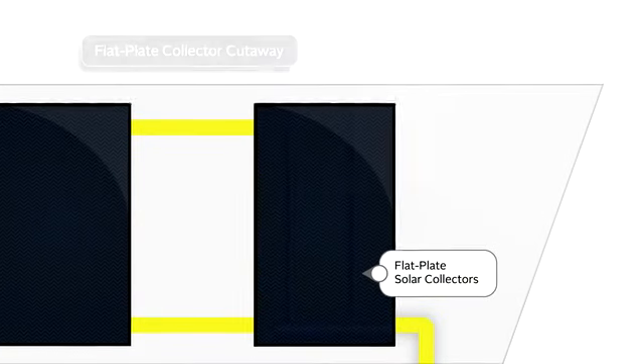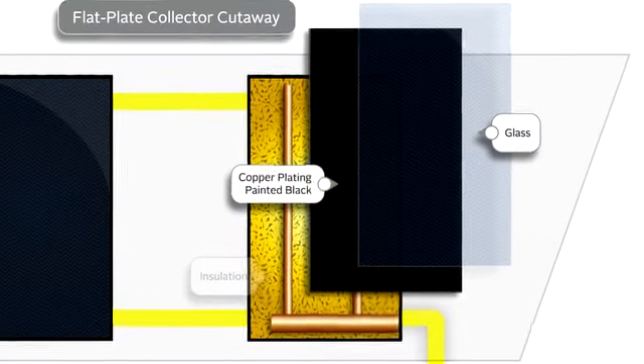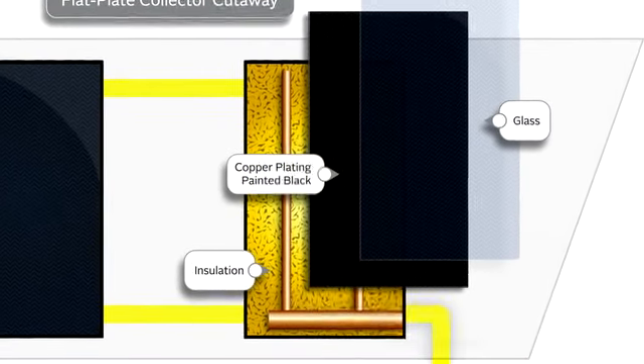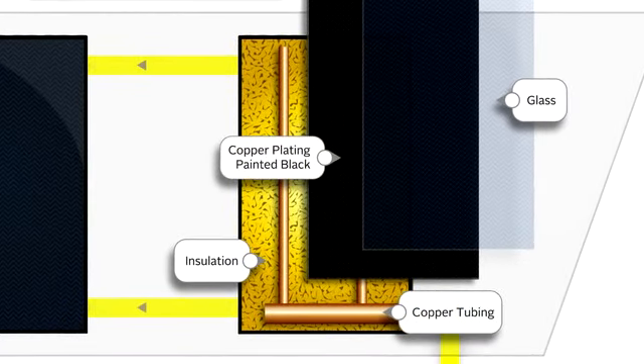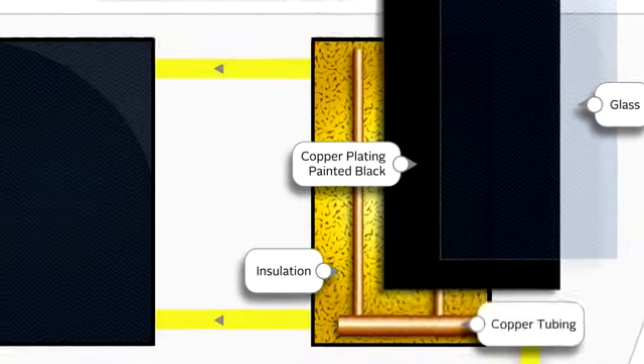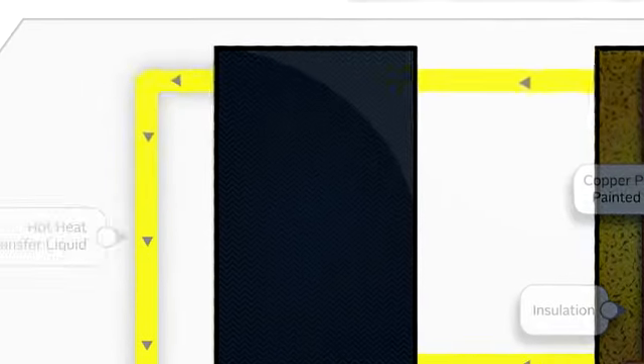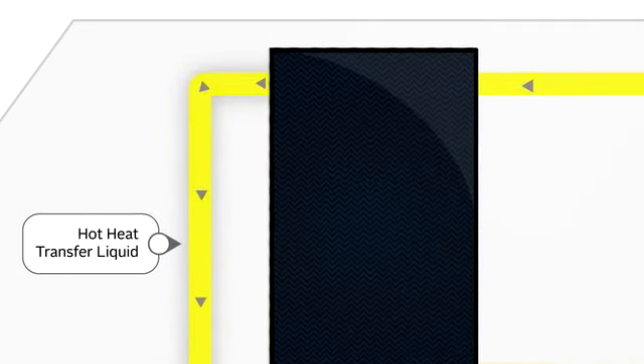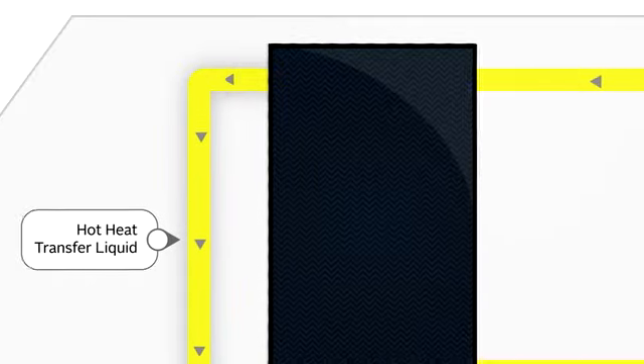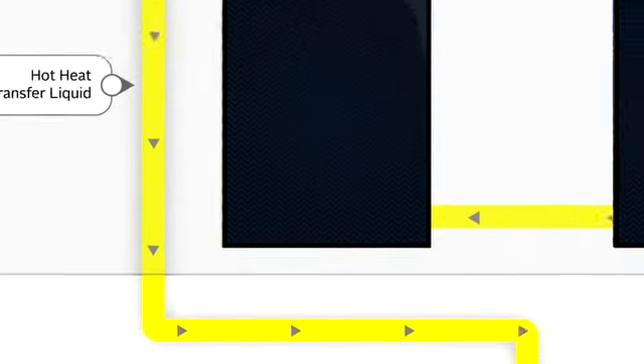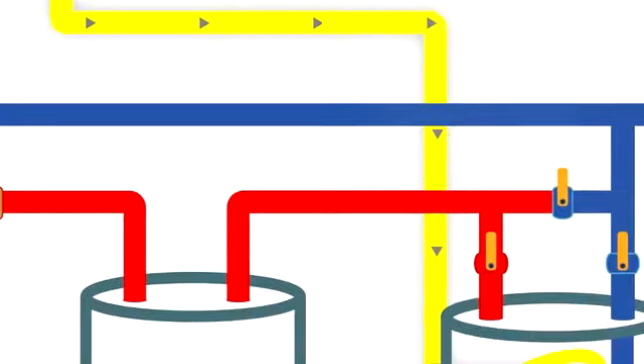These systems use flat plate solar collectors, which have a plate of glass over a heat-absorbing sheet of copper plating painted black. Underneath is a layer of insulation, and in between are rows of copper tubing that contain a non-toxic heat transfer liquid that gets hot when sunlight heats up the collectors.